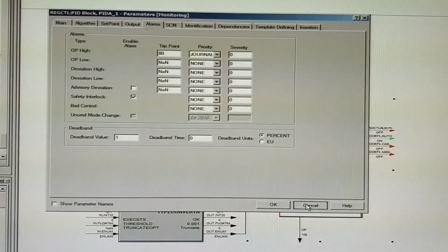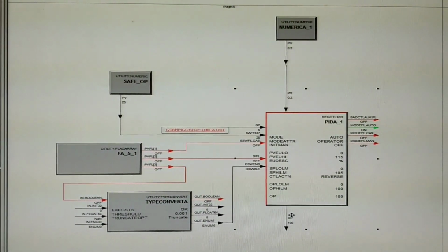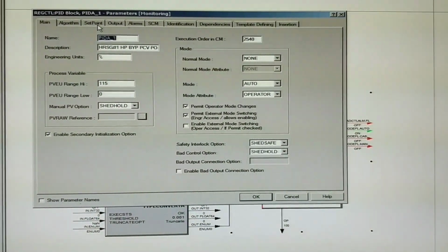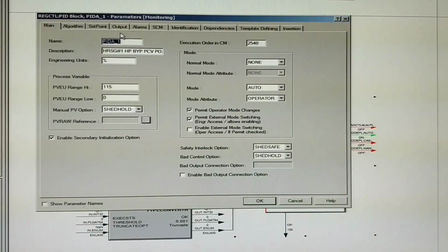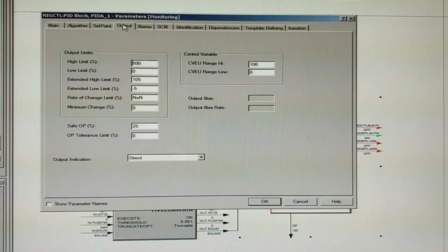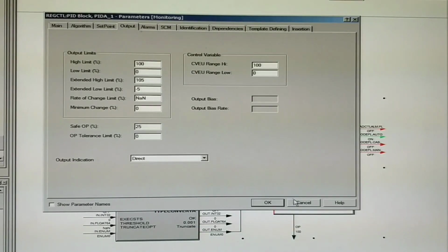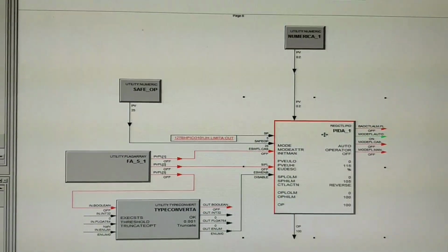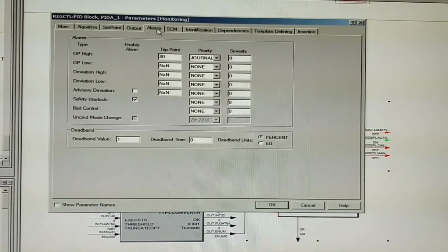So if particular control valve must not be open more than 80%, 90%, at that time, this functionality can be used. Since opening up some control valve by much more percentage will pop up the safety valves, or any process fluctuation may happen. At that time, we can use this particular alarm state to safely trip or shut down the particular plant and alarm the indication for operator knowledge.